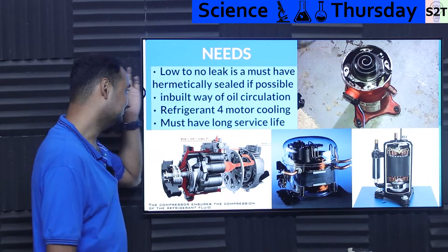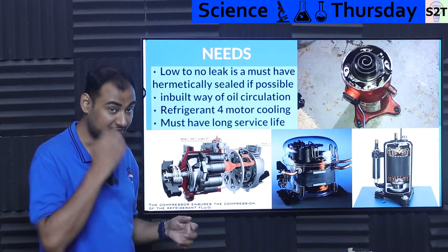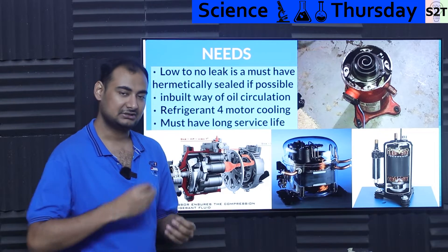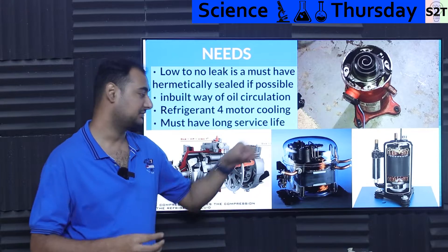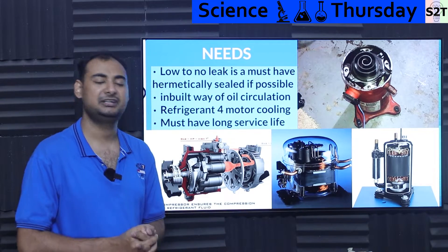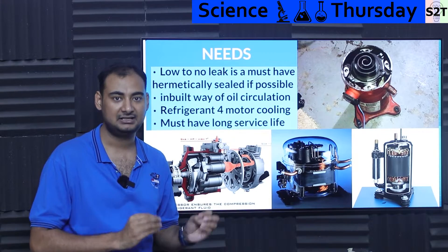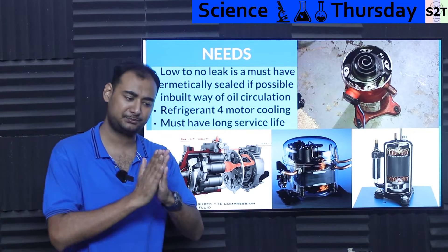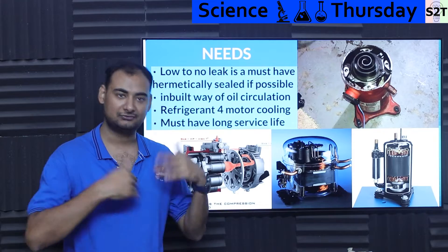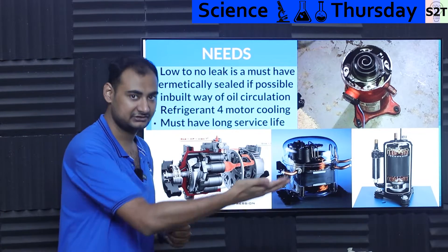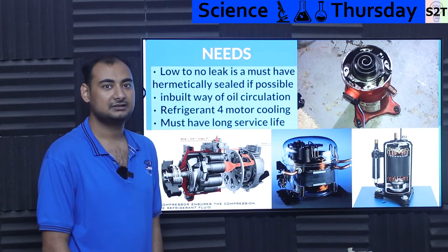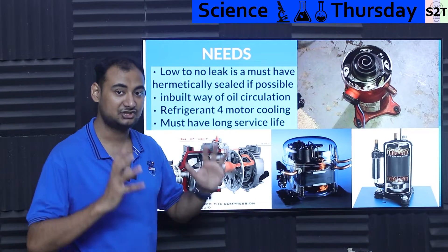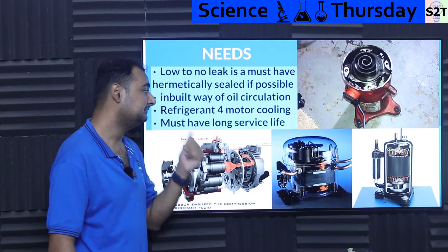You want a system that leaks very minimally. In the later 1980s, we realized that hermetically sealing everything — just sealing it completely — was the solution. Once we use copper-brazed pipes, leakage is very minimal. It will still leak eventually — metal undergoes expansion and contraction, eventually developing micro-fractures and the crystal lattice spreads apart enough for small molecules to leak — but that will happen over 15–16 years, not after six years of heavy use.